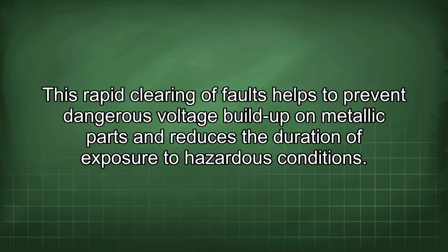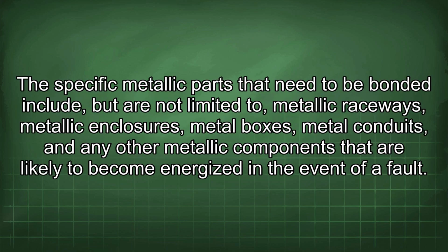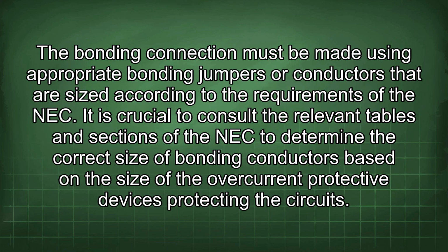This rapid clearing of faults helps to prevent dangerous voltage build-up on metallic parts and reduces the duration of exposure to hazardous conditions. The specific metallic parts that need to be bonded include, but are not limited to, metallic raceways, metallic enclosures, metal boxes, metal conduits, and any other metallic components that are likely to become energized in the event of a fault. The bonding connection must be made using appropriate bonding jumpers or conductors that are sized according to the requirements of the NEC.